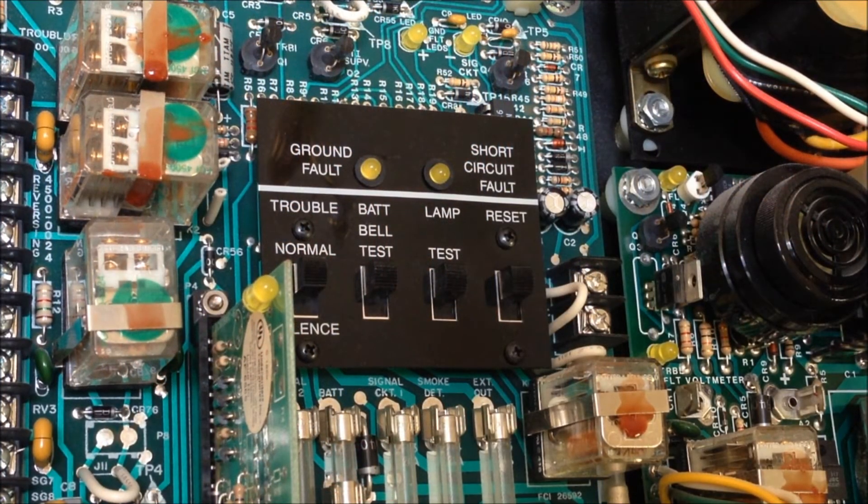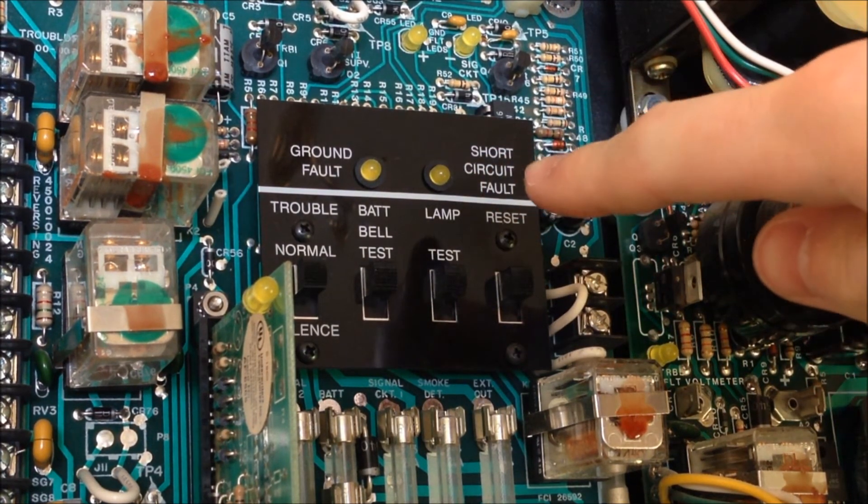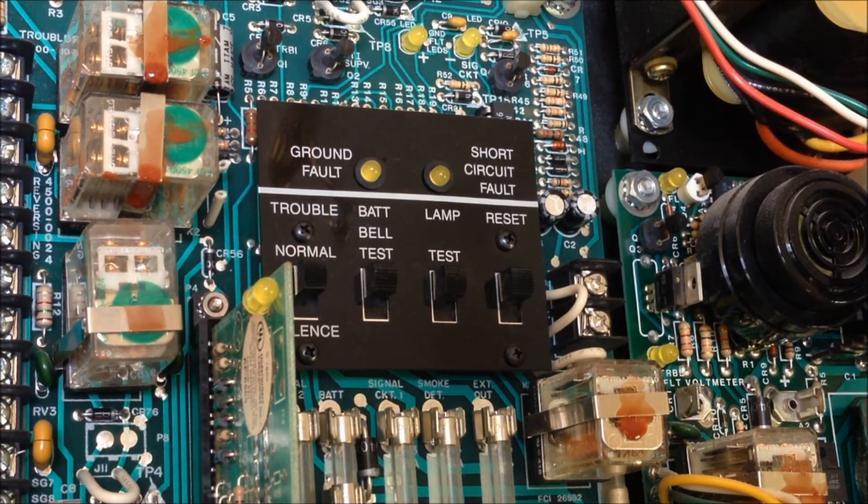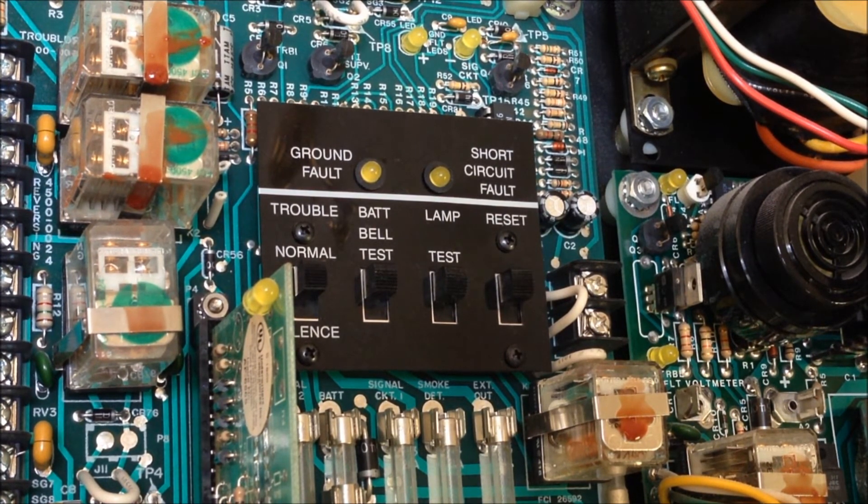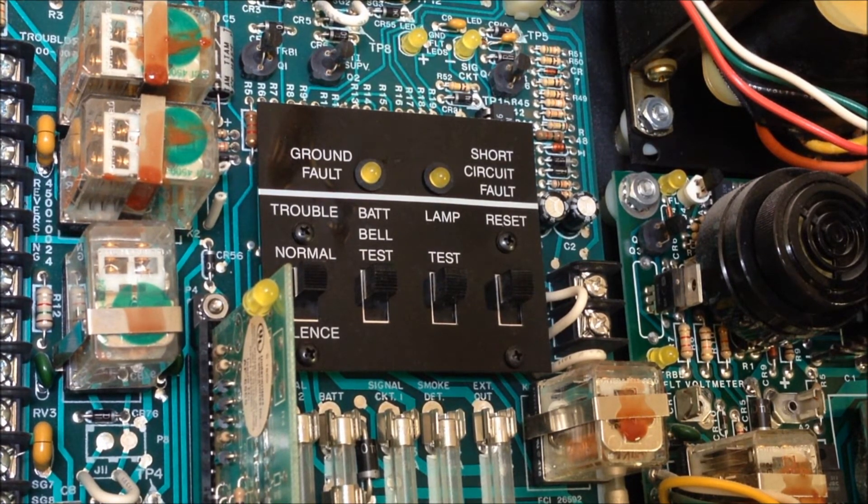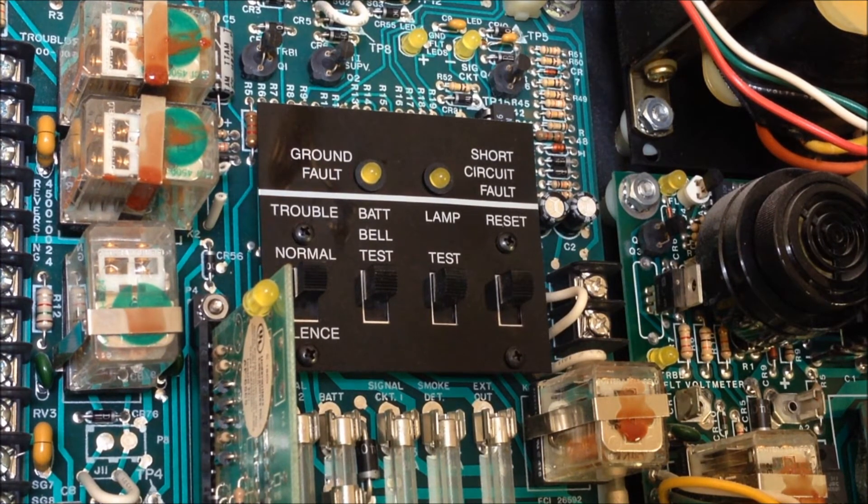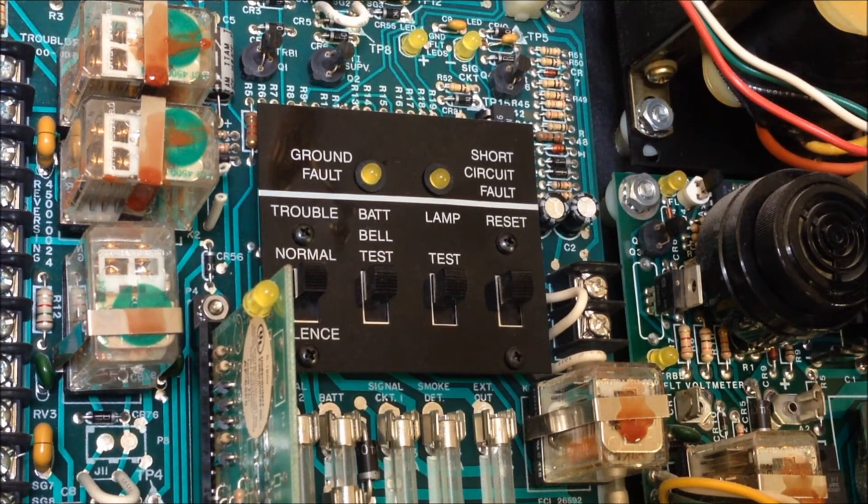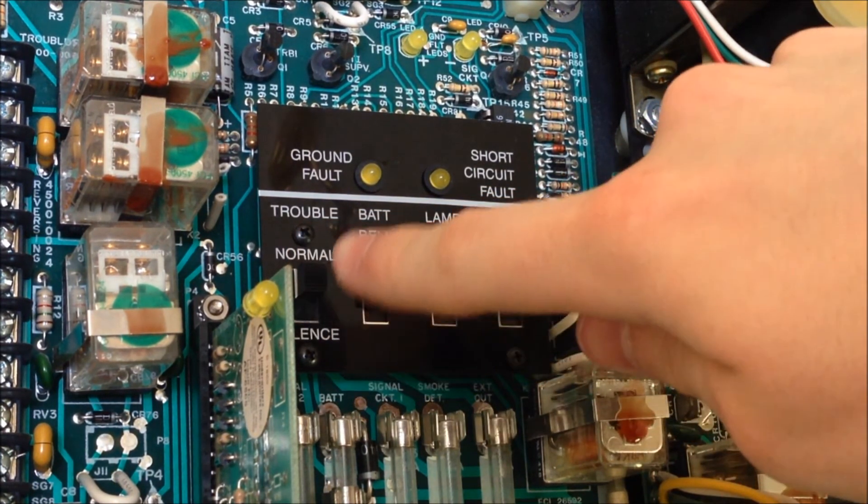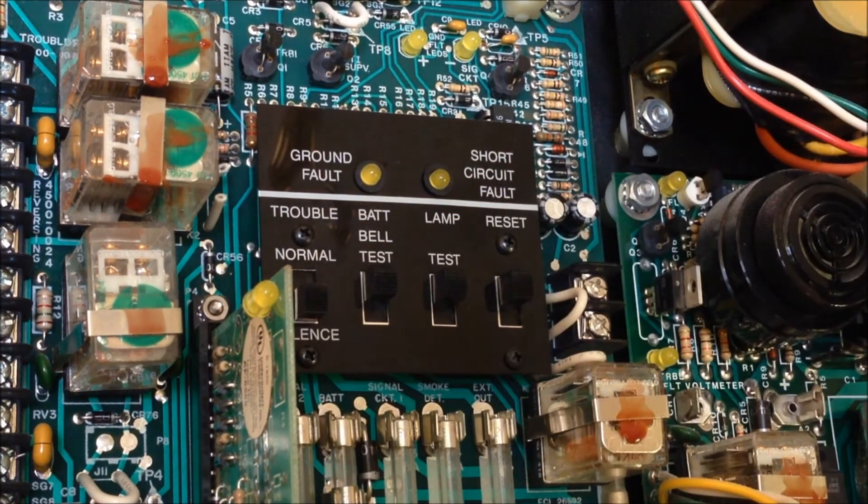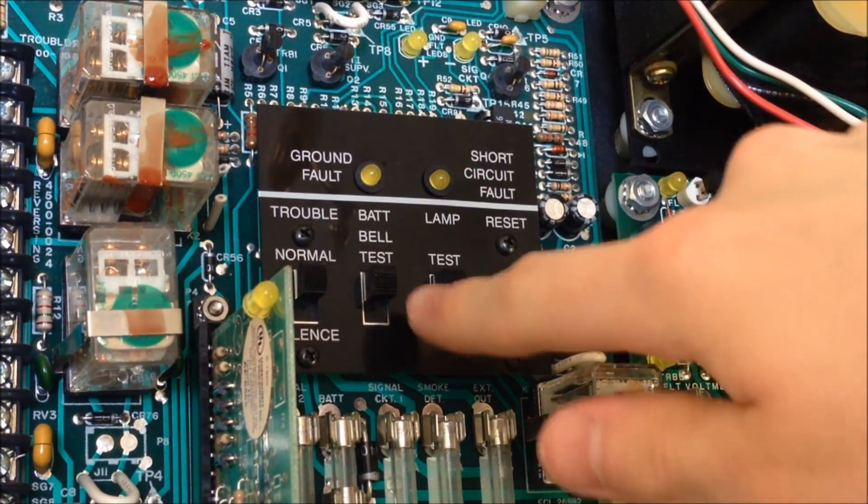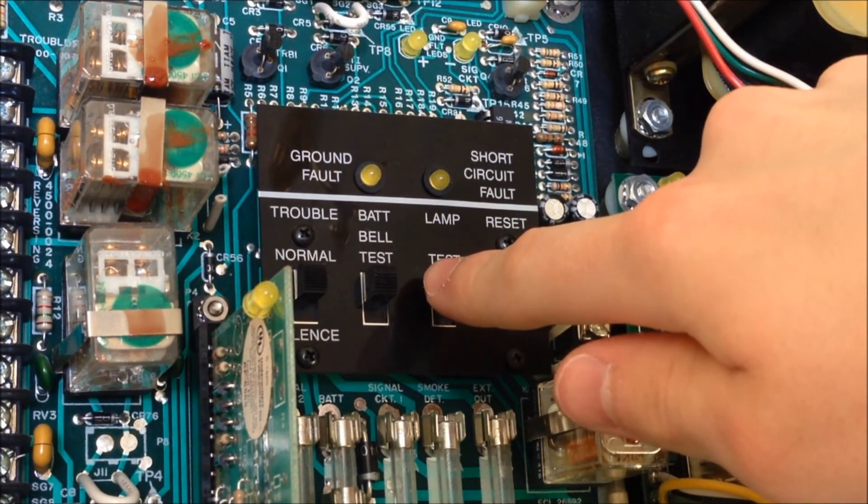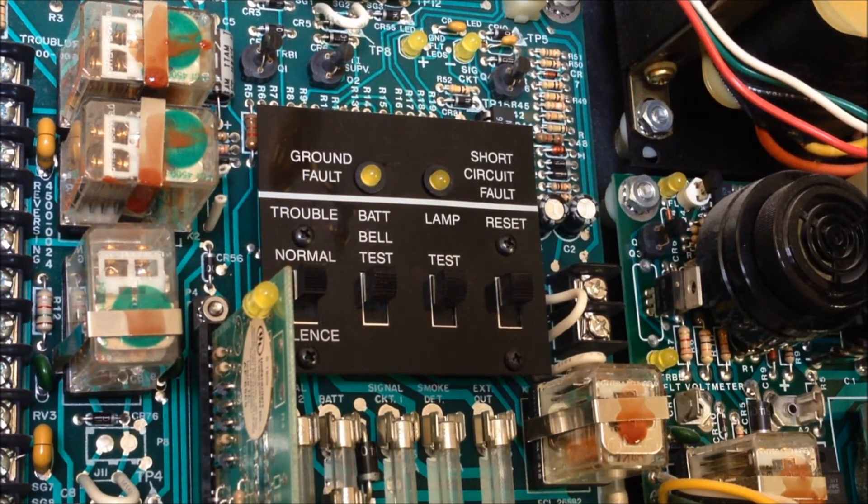Up here on that main control board I was talking about we have some troubleshooting and diagnostics LEDs. They'll light up if there's a ground fault or if there's a short circuit fault on any of the zone cards or signaling circuits, which should help to kind of let you know what the actual individual troubles that are being indicated on those circuits are, which I think is kind of a cool feature. As you can see we have the normal silent switch for the internal panel piezo. If you put it to silence when there's no troubles in the system it'll actually cause a trouble. This battery bell test switch will actually test the notification appliances off of battery power so you can make sure that there's good batteries in the system.